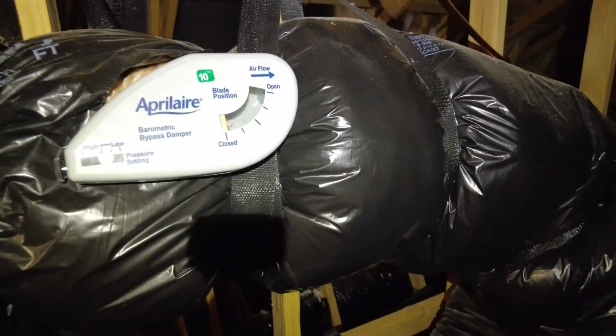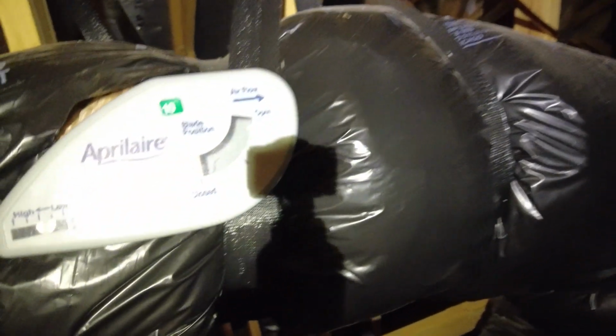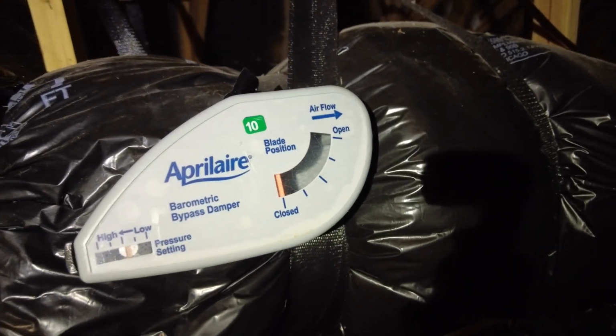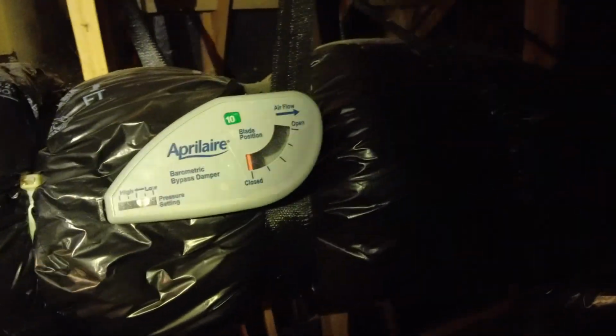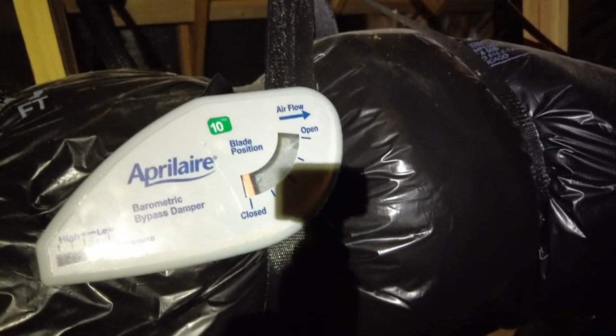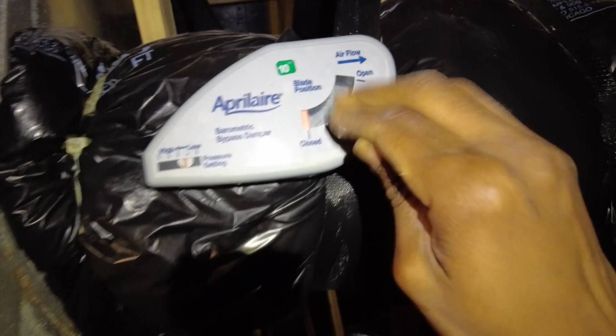Let's see if so I've got easy access to this damper here. So what I'm gonna do is keep my hand on this damper, and we'll see as I close it. You just want it to barely open and make sure it shuts back up. You see it's not shutting back up very easily. So maybe some of this insulation. Let's see. Close it manually here. See, it just barely is opening. Let it shut back up. I'm gonna try to do a little less. And I'm closing it downstairs as well. That's probably all we're gonna want right there. But I just don't like how it's not closing up all the way. So that's more than likely what happened. Someone overdid it because it's just not closing properly.